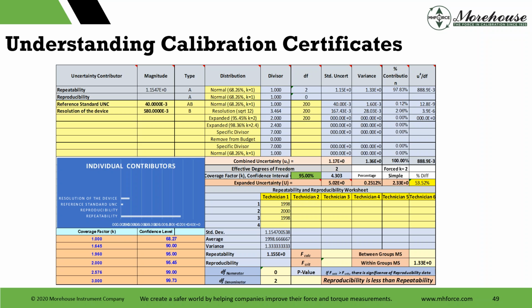In this example we're running through the Welch-Satterthwaite equation, which is recommended by the GUM. And if we look up a T-inverse formula, it is basically telling us, for the reference standard uncertainty and the resolution of the device, that if our uncertainties are Type A, and we did a repeatability study and took 3 measurements, the appropriate coverage factor we would need to use is not 2, but 4.303. And if we just use 2 instead of running it through this formula, we would have a difference of around 53.52% in the uncertainties. So much different. One time we're going to say the expanded uncertainty is 2.33. The other time we're going to say it's 5.02. So blindly multiplying by a coverage factor of 2 may seriously underestimate your uncertainty.